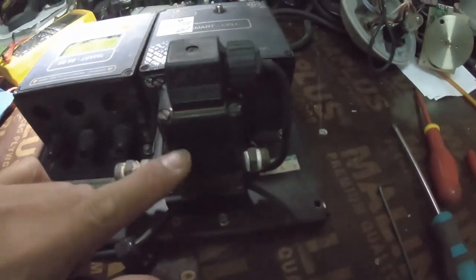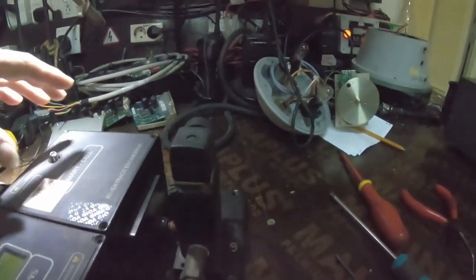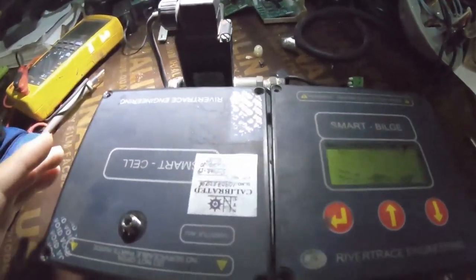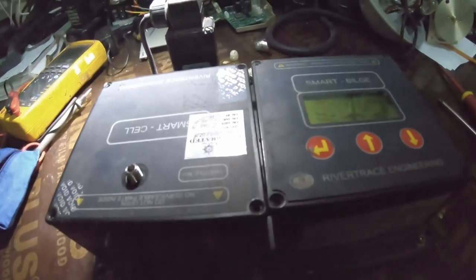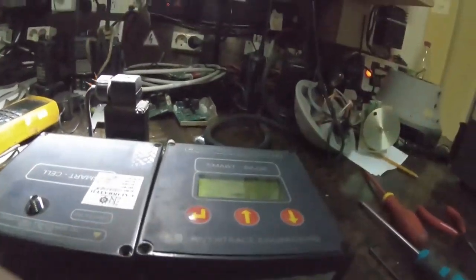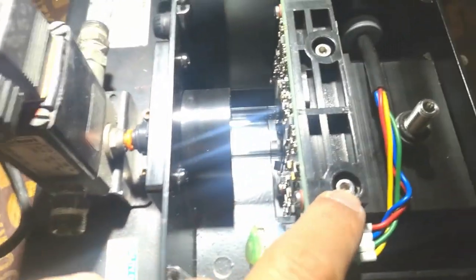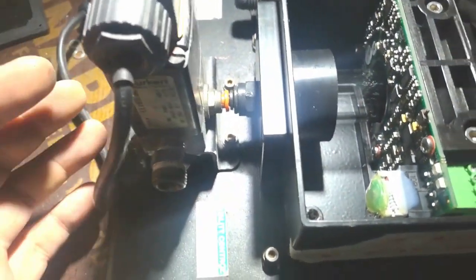This is the part number. This is the three-way valve. I'll open this and show you what is inside and how to clean it. I will dismantle it all so you can see, and you can also try to open this and clean it by yourself. Just put back the two screws and that's the procedure for how to clean the cartridge of this sensor glass.